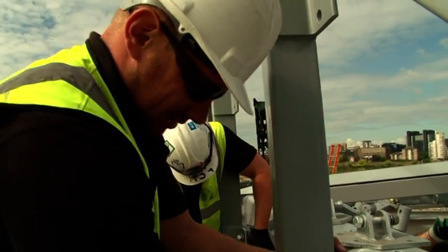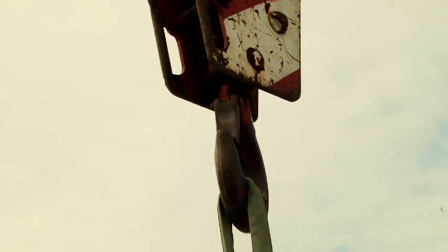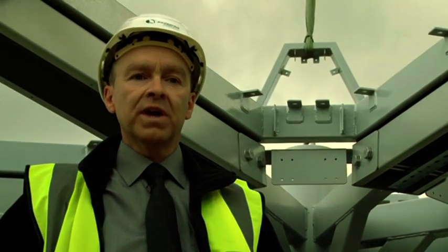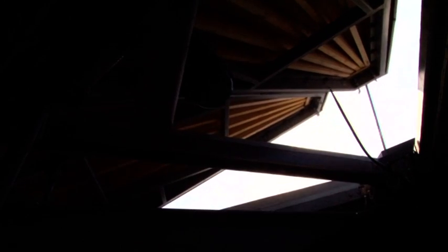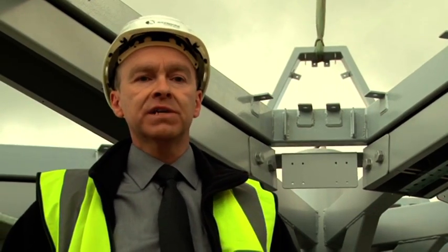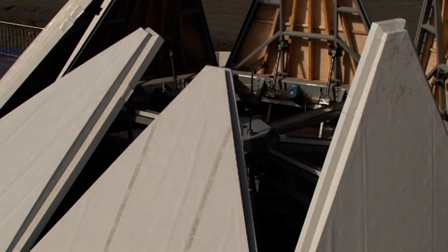It's 8.5 metres in diameter and the whole unit had to open within 60 seconds. When there is a fire in the tunnel, the system will be engaged in a specific mode to get rid of the smoke. The component above me is one of the segments of the smoke ventilator — it is shaped similar to a petal. We decided during the design process to open all eight petals in a cascade, which keeps the power very low.